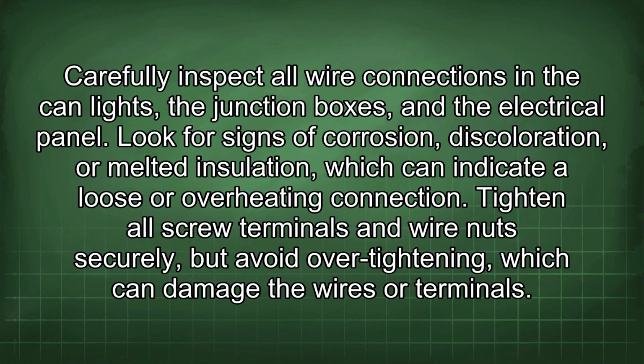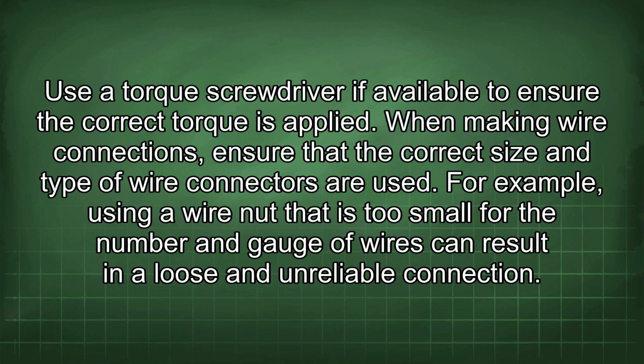Carefully inspect all wire connections in the can lights, the junction boxes, and the electrical panel. Look for signs of corrosion, discoloration, or melted insulation, which can indicate a loose or overheating connection. Tighten all screw terminals and wire nuts securely, but avoid over-tightening, which can damage the wires or terminals. Use a torque screwdriver if available to ensure the correct torque is applied. When making wire connections, ensure that the correct size and type of wire connectors are used. For example, using a wire nut that is too small for the number and gauge of wires can result in a loose and unreliable connection.